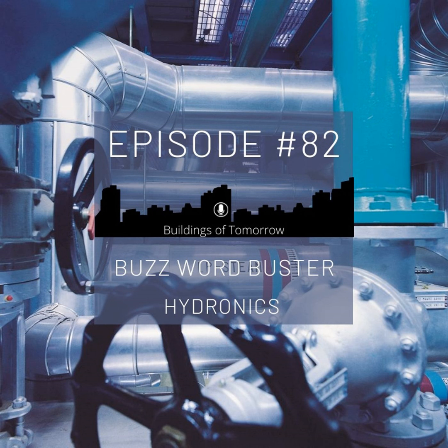And if we see, for example, that all these valves are throttling down to maybe 40%, this is a clear indicator that the pump at the producer puts way too much pressure into our network because all the valves have to hold against that pressure. So by knowing that, we then can go back through the building automation system and continuously lower the pump speed, for example, by resetting the pressure differential set point for this pump.